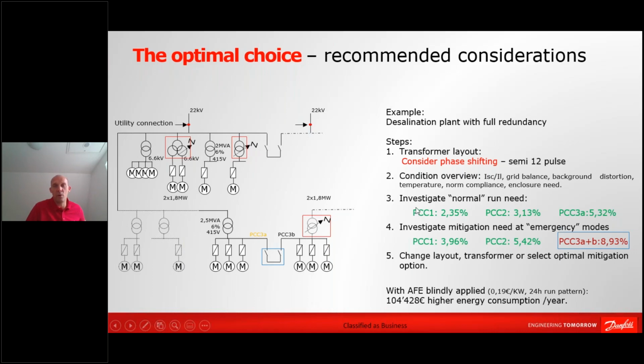It's only when I have the emergency mode that I need mitigation. So when one of the transformers is shut down or out of service or exploded or for other reasons, and everything is fed from one transformer, then if you do the same analysis, you can see that one of the load points down here actually becomes into the red zone with a very high voltage distortion. And that means that you can actually apply an active filter down here that you only activate when you're running in emergency mode. And that means if you do this, instead of just putting AFE blindly to everything here, the investment that you can save is significant.